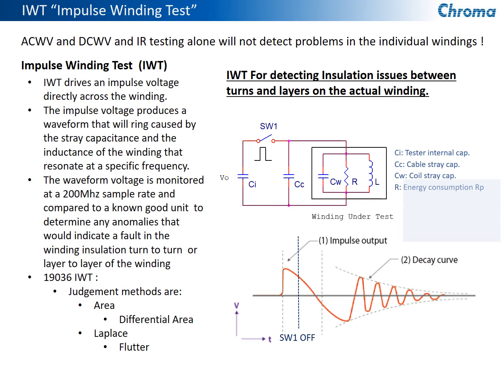The other thing that we do with this unit, because AC and DC high-pot testing and insulation resistance testing alone cannot detect all types of failures, especially failures within the winding itself, is that the impulse winding test is included for that. If you're not familiar with impulse winding test, we apply a high voltage for a short duration right across the inductor, driving the winding, and while we do that and then remove it, we look for the voltage waveform that is generated. And what we'll see, like the one you see here, is the instantaneous voltage right at this point, which is a very quick rising edge, and it goes up to the peak voltage applied.